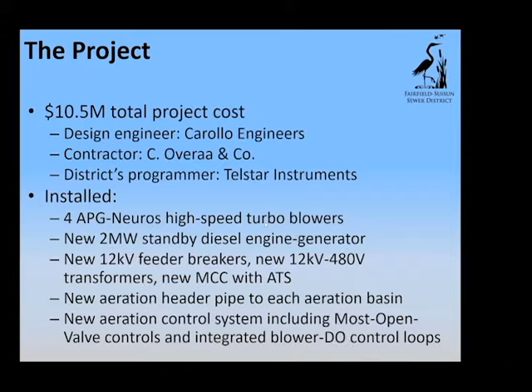We essentially addressed all those elements we just talked about: 4 new high-speed turbo blowers to replace our old aging blowers, a new 2 megawatt standby diesel engine generator, new electrical equipment. We installed a new aeration header pipe to distribute that air to all the places it needed to go, and a new control system that included this most open valve component, and better integrated our blower controls with the aeration system controls in general.